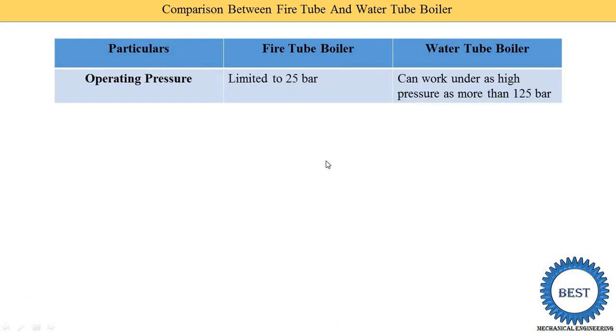This is the first comparison. The second comparison is on the basis of operating pressure — meaning the pressure at which the boiler is working. Fire tube boiler is operated at limited to 25 bar, meaning up to 25 bar the fire tube boiler works. And water tube boiler can work under as high pressure as more than 125 bar. This is the range of pressure for both boilers.